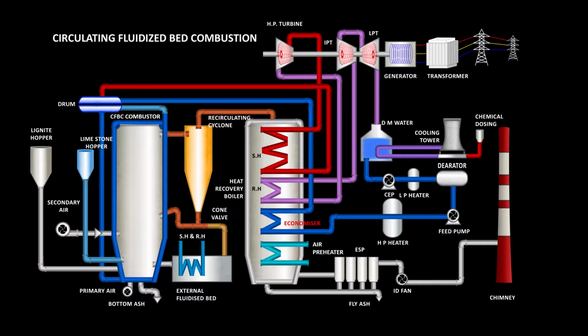Circulating fluidized bed combustion. The firing system of these boilers differs from the pulverized fuel firing boiler. The lignite, which is less than 10 mm in size, is fed into the combustor directly. Nearly 550 tons of bed material, of size ranging from 0.2 mm to 1 mm, is already charged in the combustor. The primary air supplied through a number of nozzles provided at the bottom of the combustor fluidizes the lignite along with bed material.